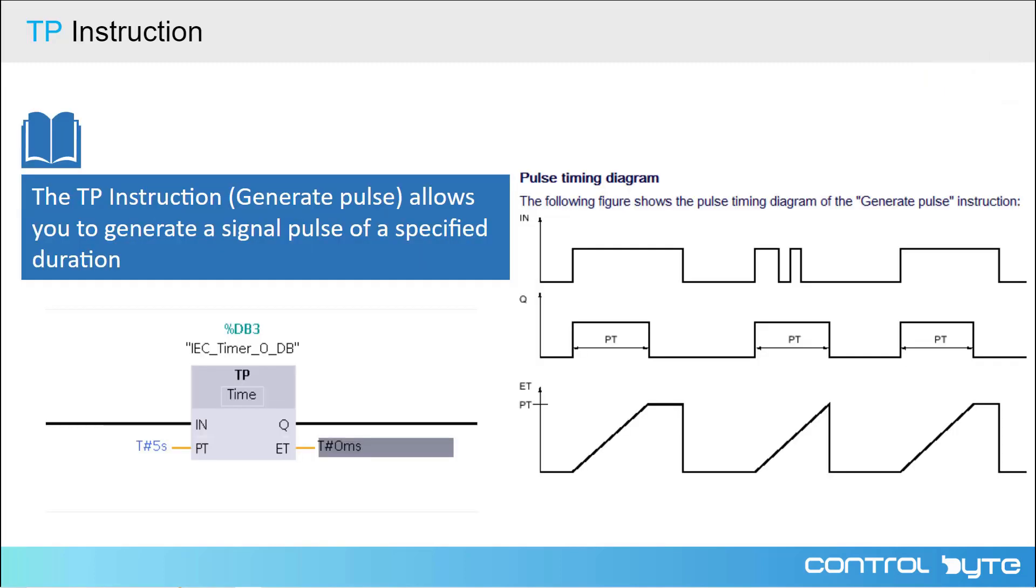Let's start with the TP instruction that allows you to generate a signal pulse of a specified time duration. In the memory of PLC, such a timer is declared as a DB block. The symbol of timer has two inputs, IN and PT. On the IN input, we add result of last logic operation. On the PT input, we add the time that specifies duration of our pulse on output.